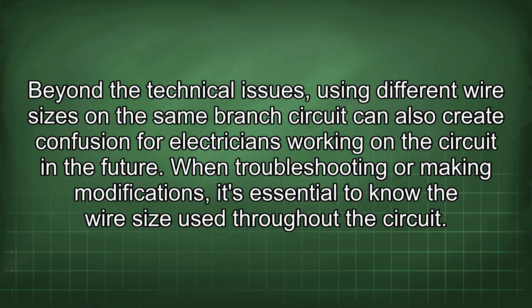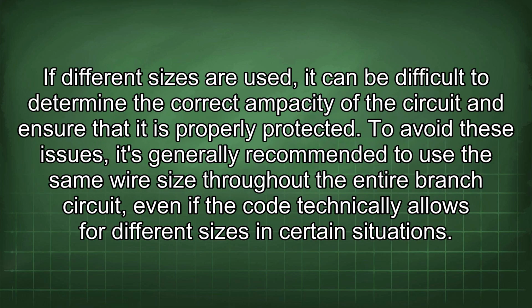Beyond the technical issues, using different wire sizes in the same branch circuit can also create confusion for electricians working on the circuit in the future. When troubleshooting or making modifications, it's essential to know the wire size used throughout the circuit. If different sizes are used, it can be difficult to determine the correct ampacity of the circuit and ensure that it is properly protected. To avoid these issues, it's generally recommended to use the same wire size throughout the entire branch circuit, even if the code technically allows for different sizes in certain situations.